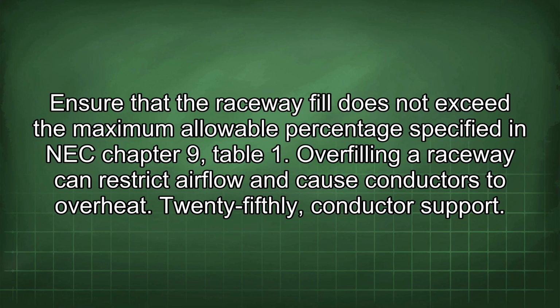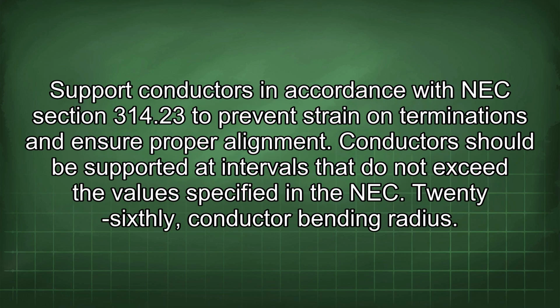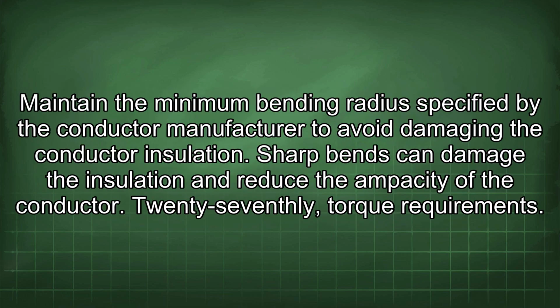25th, conductor support. Support conductors in accordance with NEC Section 314.23 to prevent strain on terminations and ensure proper alignment. Conductors should be supported at intervals that do not exceed the value specified in the NEC. 26th, conductor bending radius. Maintain the minimum bending radius specified by the conductor manufacturer to avoid damaging the conductor insulation. Sharp bends can damage the insulation and reduce the ampacity of the conductor.